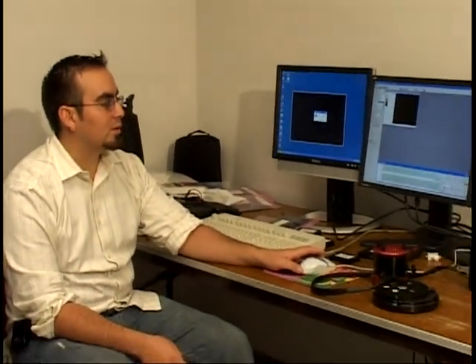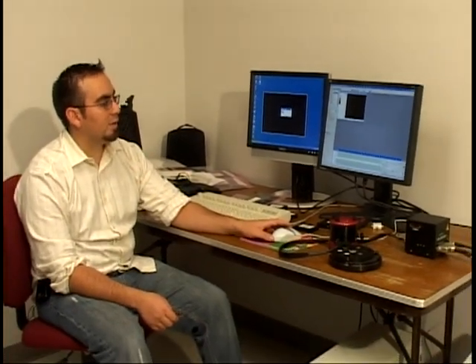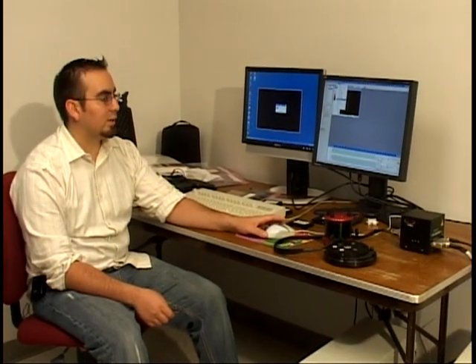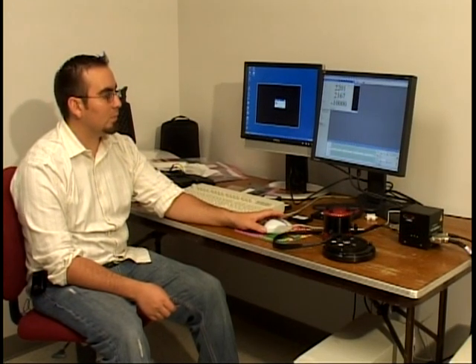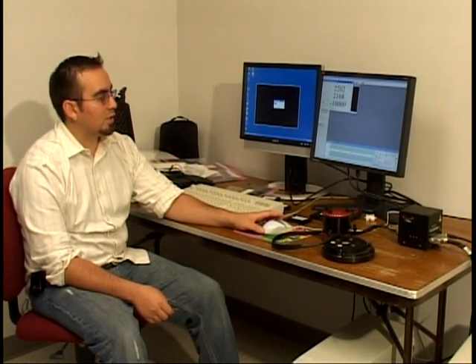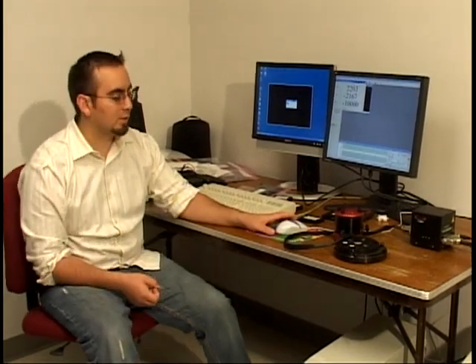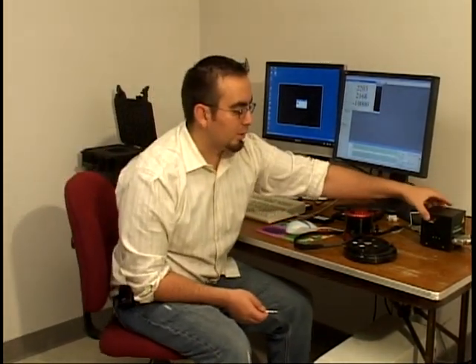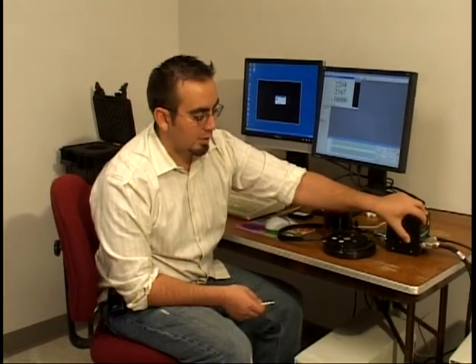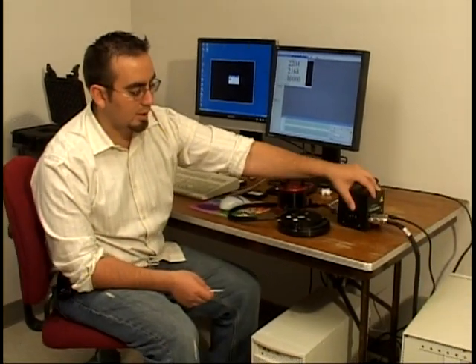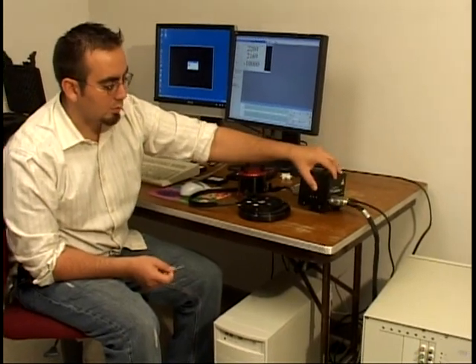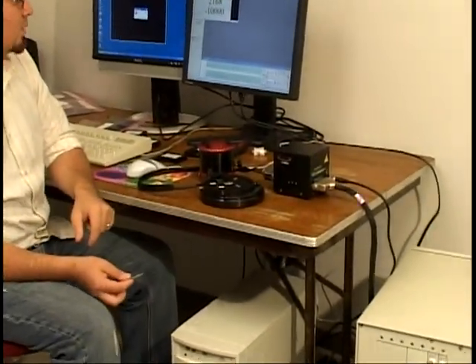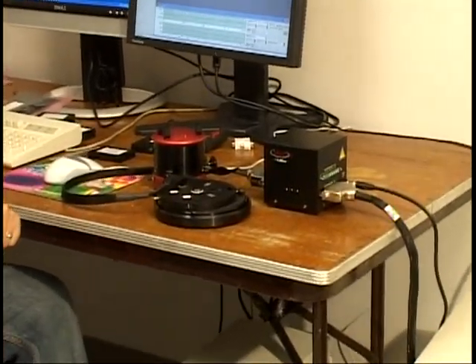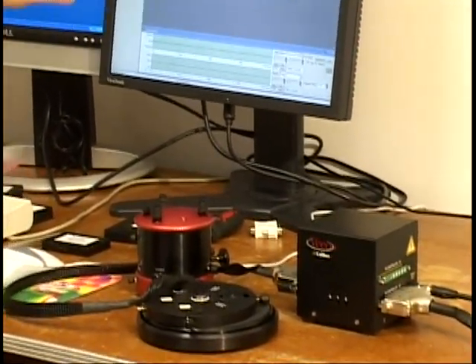Before you open up that window, you got to make sure you're in the 1 micron scan range. So using the drop-down menu, select 1 micron. Then you can go to the setup XY alignment. The only ones we're going to adjust are the X and Y using the software linearized file. To do that, on the side of the brick, there's an X, Y, and Z. There's X, Y, and Z holes. Inside those holes are actually screws for adjusting the pots. What you want to read is at least 2.3 volts for X and Y, so adjust.